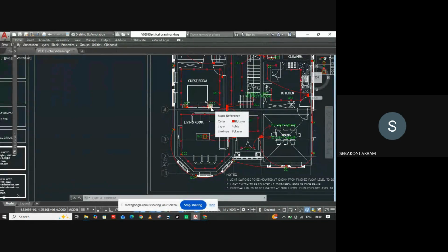So 30 times 10 watts, that's 300 watts, which is about 1.2 amps. Are we together, Martin? With this calculation, because it is really, really important.